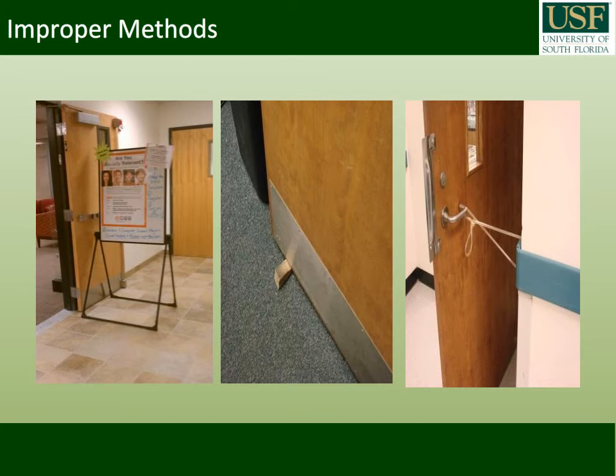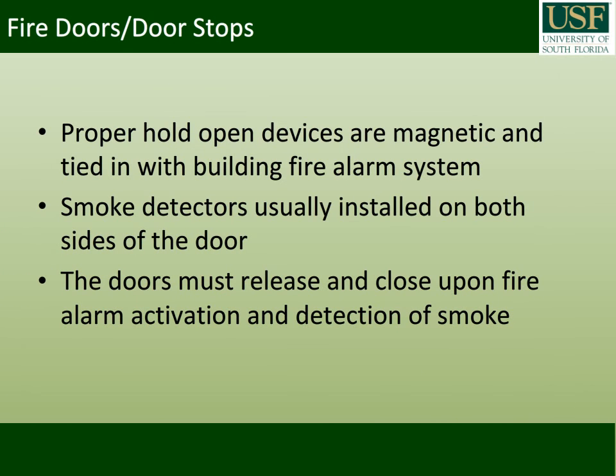These are all unapproved methods. Fire doors should not be held open and nothing should be in the way impeding the door from closing. If a fire door must stay open, there are proper methods available. Proper hold-open devices are magnetic and tied in with the building's fire alarm system. Smoke detectors are usually installed on both sides of the door. The doors must release and close upon fire alarm activation and detection of smoke.